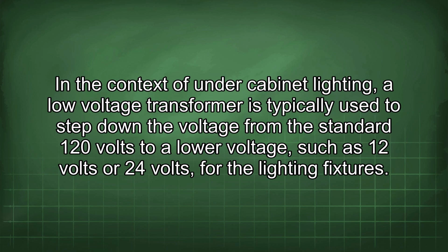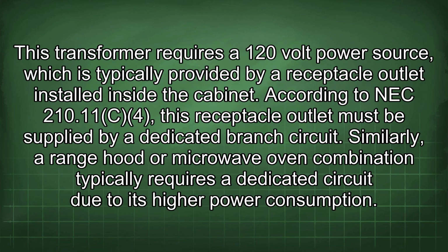In the context of under-cabinet lighting, a low-voltage transformer is typically used to step down the voltage from the standard 120 volts to a lower voltage, such as 12 volts or 24 volts, for the lighting fixtures. This transformer requires a 120-volt power source, which is typically provided by a receptacle outlet installed inside the cabinet. According to NEC 210.11(C)(4), this receptacle outlet must be supplied by a dedicated branch circuit.